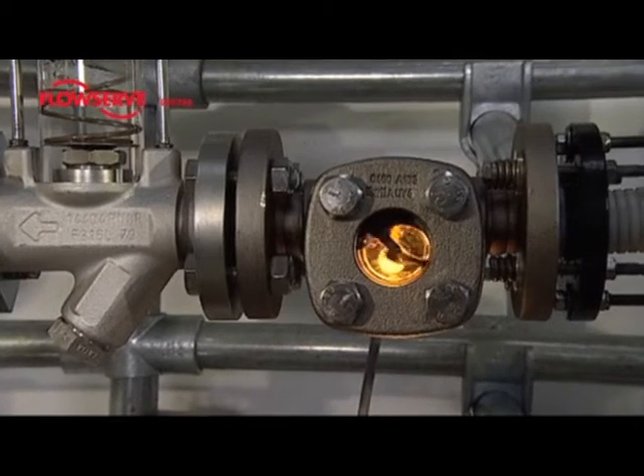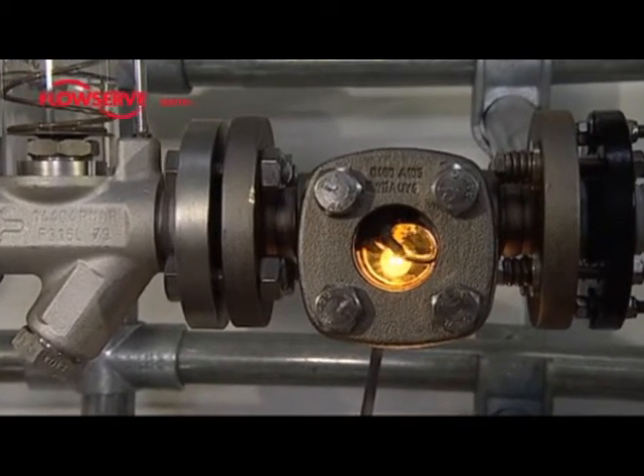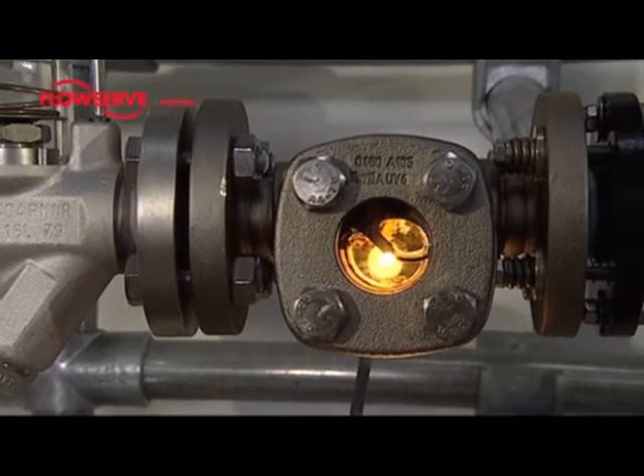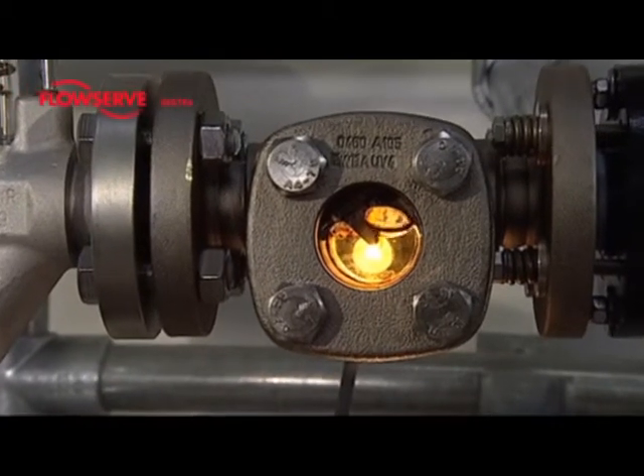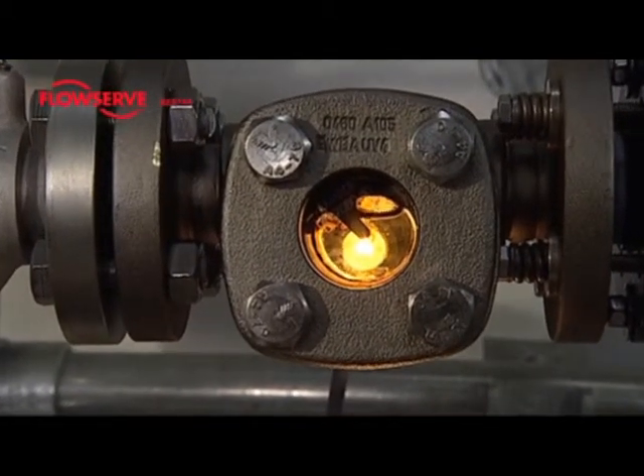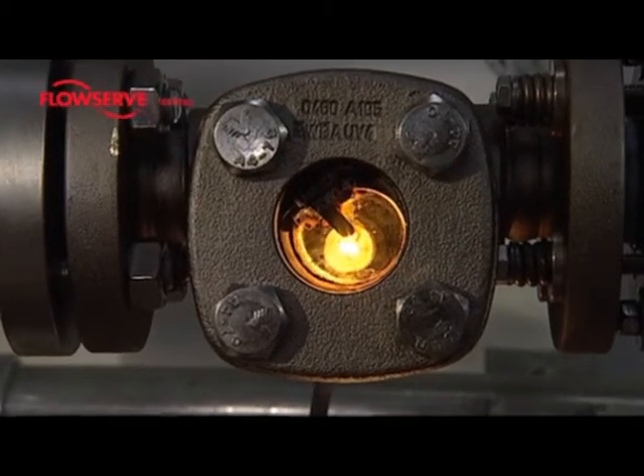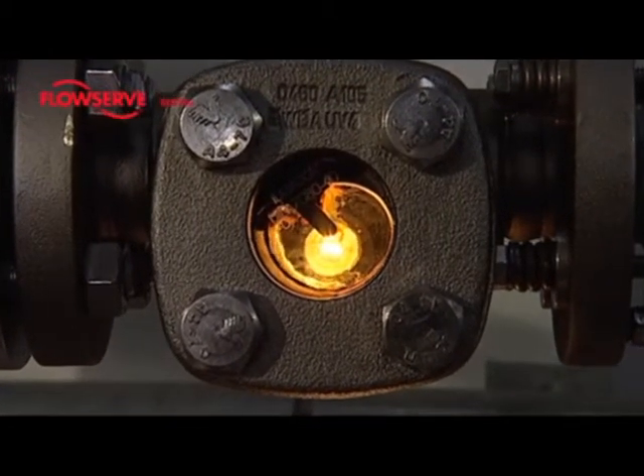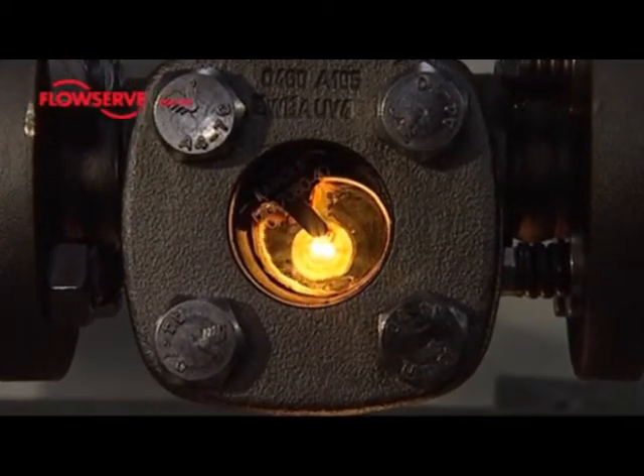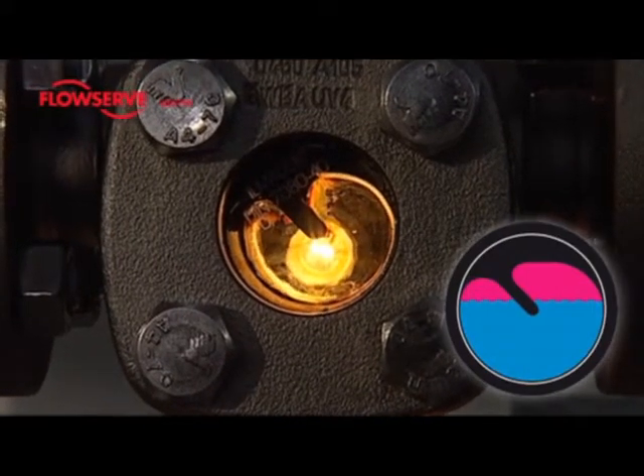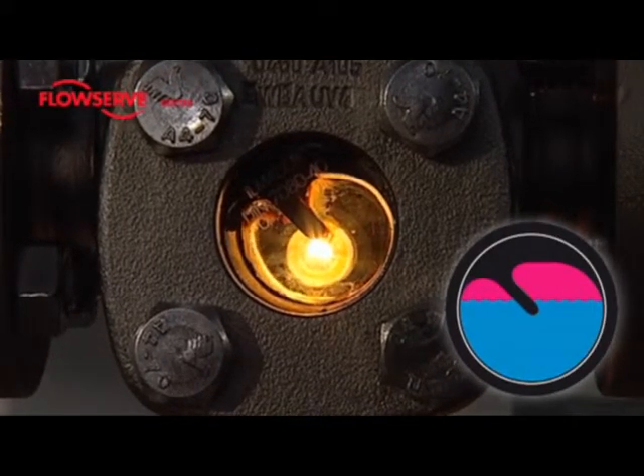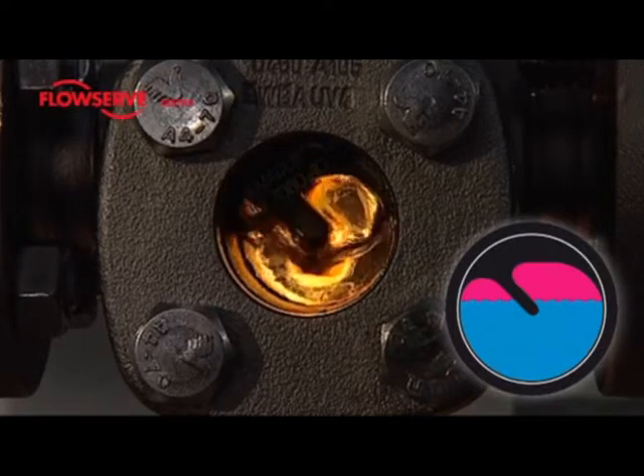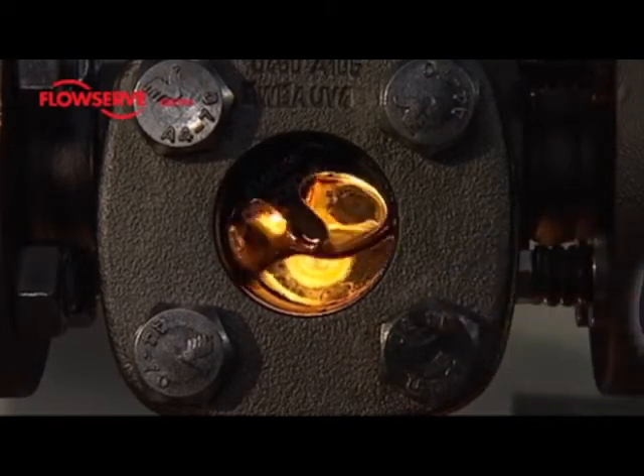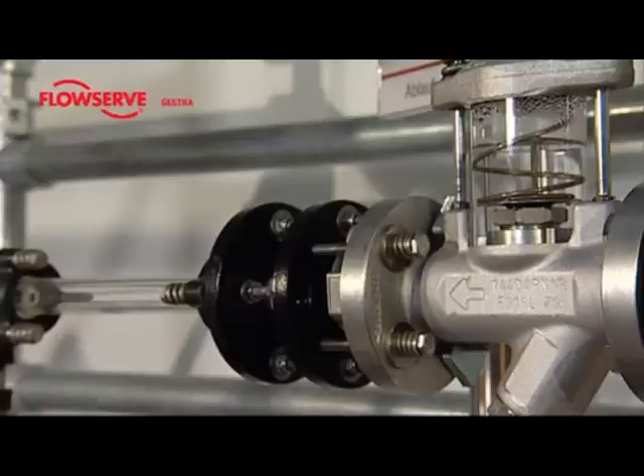A Vaporscope VK16 sight glass is mounted upstream of the traps. This is used for monitoring the steam traps and making the flow processes visible. A deflector inside the Vaporscope sight glass forces the condensate to flow through a small siphon. A small steam space is formed in front of the deflector, and the deflector is slightly immersed in the condensate. The following steam trap discharges only condensate. Steam does not pass below the deflector.